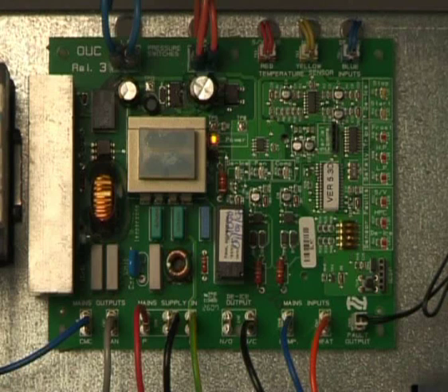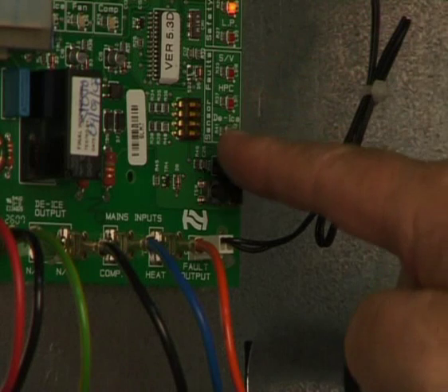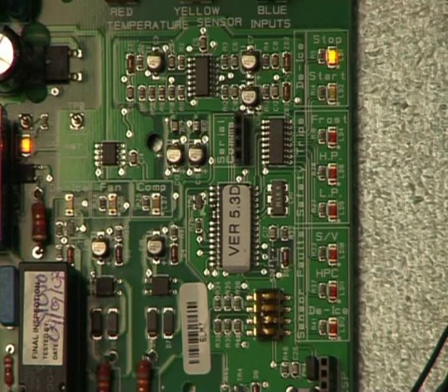Located just below the column of LEDs is the test button. The test button functionality is as follows. By pressing the test button for a full 12 seconds in any mode, the OUC will be set in a commissioning mode. This reduces many of the running timers so that commissioning can be done without continuously being impeded by the time delays each time the compressor and heat signals are switched. The commissioning mode is allowed to run for 30 minutes, after which time normal operation resumes. While in commissioning mode, the column of LEDs will flash once every 5 seconds.